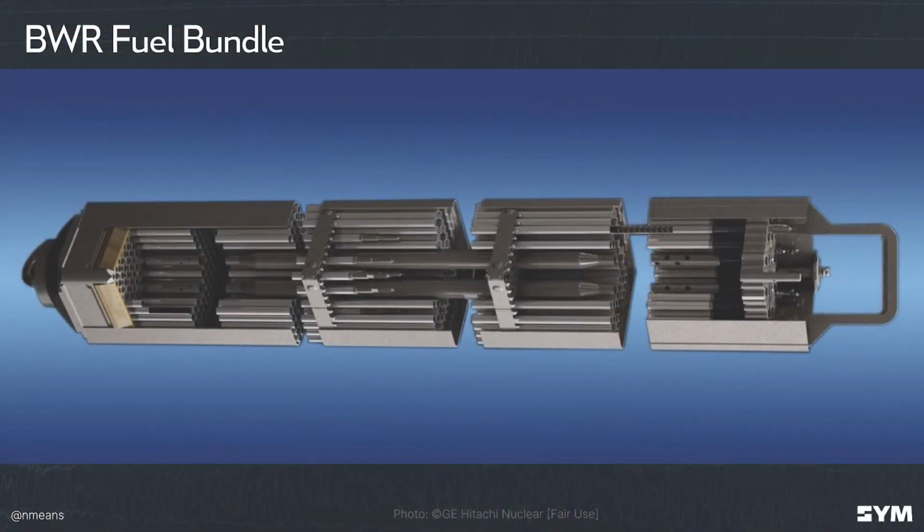The fuel rods in most nuclear reactors are tubes made of zirconium alloy and filled with uranium fuel pellets. Zirconium is the metal of choice for this application because it's very corrosion and heat resistant, while also being essentially invisible to the neutrons that power the nuclear chain reaction in the core. As the core gets hot enough to melt, though, something important happens to the zirconium. It loses its ability to resist corrosion and starts rapidly corroding. And this rapid corrosion in a steam-filled reactor pressure vessel rips the water molecules around it apart into zirconium oxide and hydrogen gas.